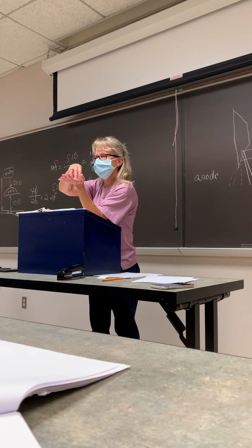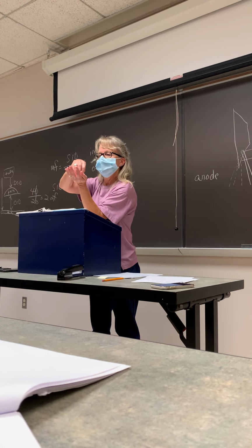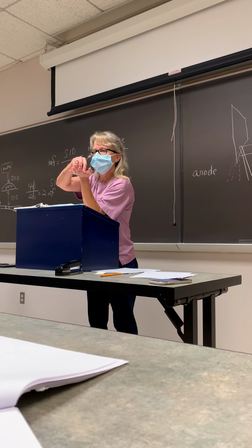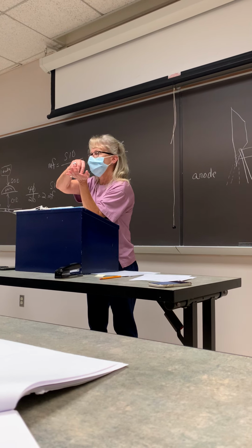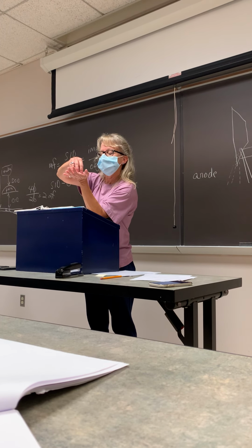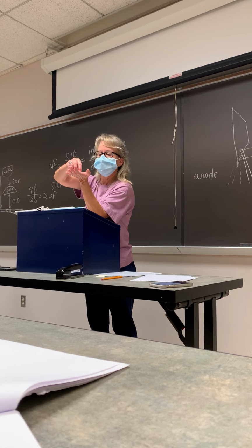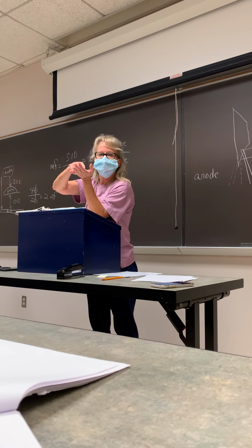Okay, that's what an AEC is, automatic exposure control. So basically, what thing don't you have to use on the control panel if you don't want to? mAs or kVp? mAs. Because when a certain amount of x-rays hits that ionization chamber, it shuts the exposure off.